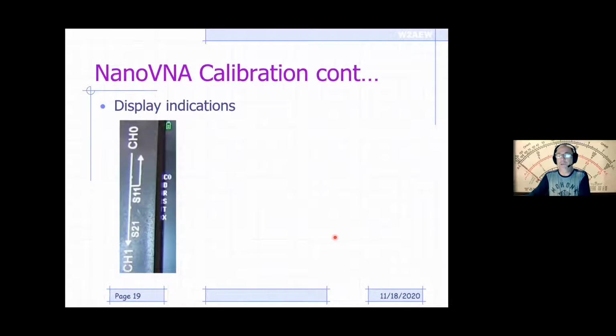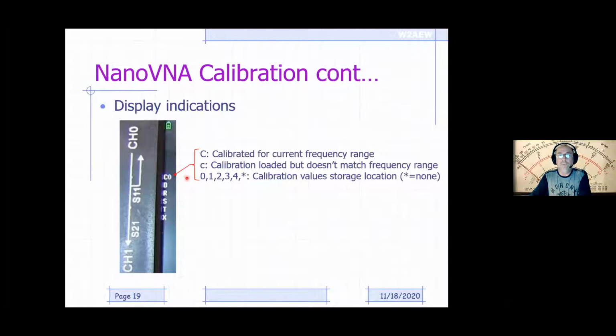So this is a couple more details of what that calibration looks like on the instrument itself. On the display, there's a little column of digits that appear on the left-hand edge. And the first line will show a capital C when the frequency range you've got set up is a calibrated frequency range, meaning that the calibration loaded is valid over that particular range. If you've got a calibration loaded, but it doesn't match the frequency range that you've got set up, it'll be a small letter c, which indicates that you're calibrated, but you're probably interpolating because the frequency range doesn't match. The number following that indicates the memory slot that the calibration you're using is stored in.